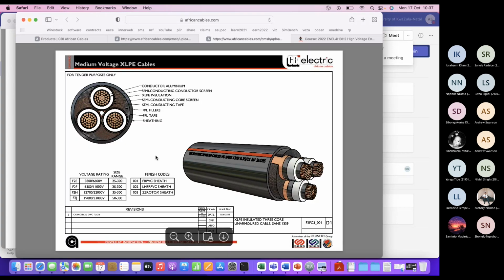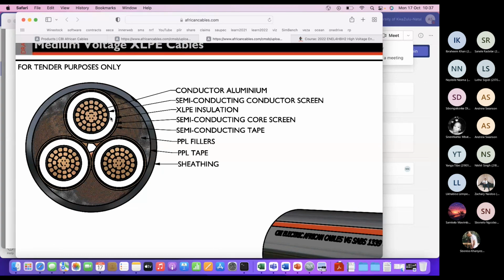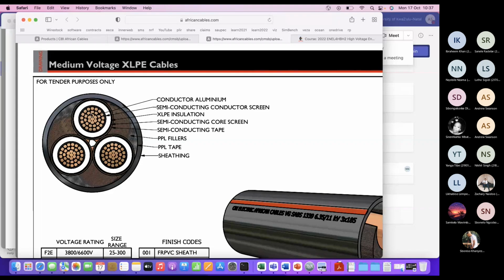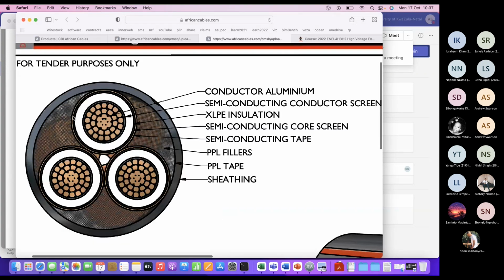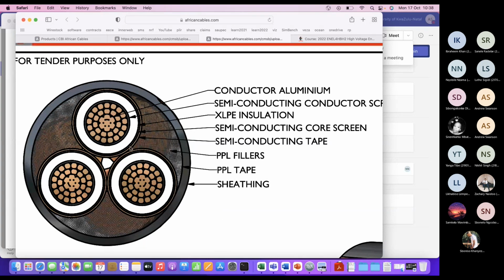An XLPE cable, also 3-phase. You can see it looks a little bit different. I'm not sure why I've selected the aluminium one, but in the middle there, you can see the round conductor. It's a copper or an aluminium conductor. Then that white bit there, that's the XLPE insulation. Right, it's the dielectric. In between the conductor and that insulation, there's a semiconductor screen, as well as on the outside of that. Then there's a screen on the outside. You can see a little copper line there. Right, so that's the single phase cable.